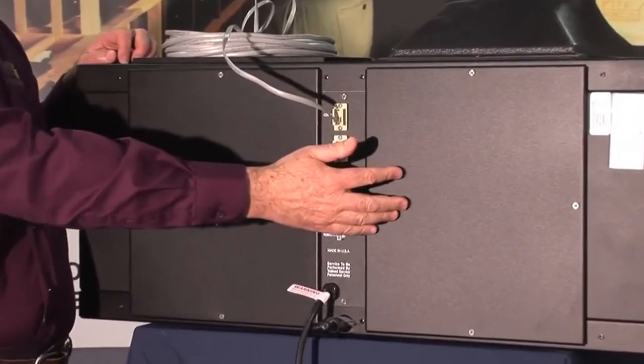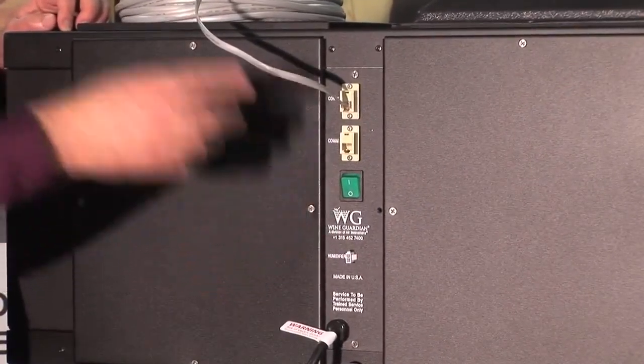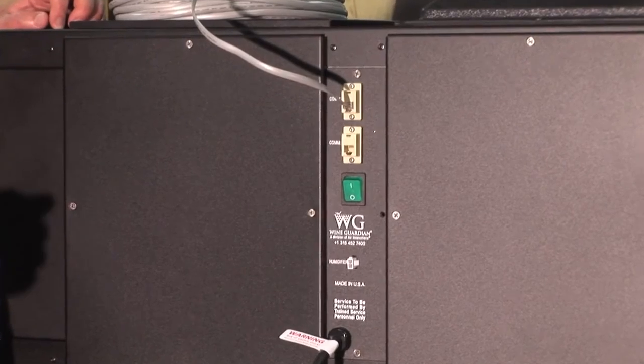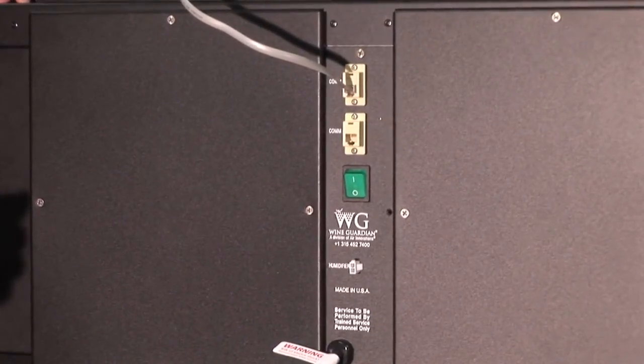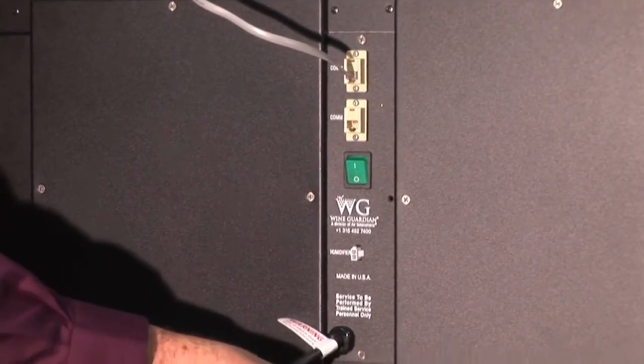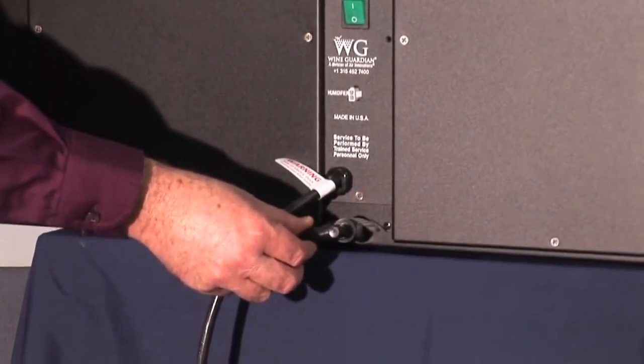I mentioned that it's generally installed using one of these removable panels, but it is possible to install the humidifier directly inside the wine cellar. The condensate drain is right here. You do not need to trap it. It's internally trapped.